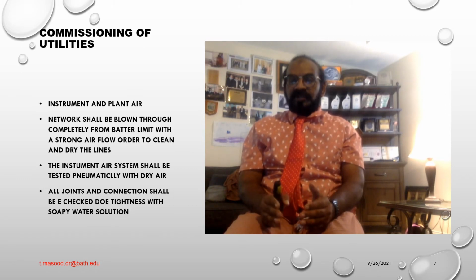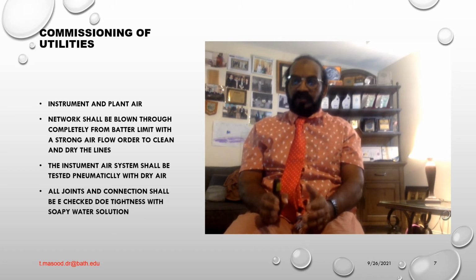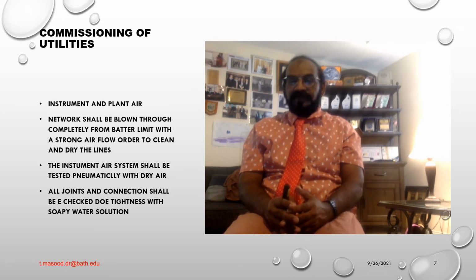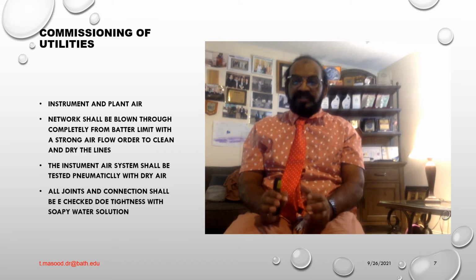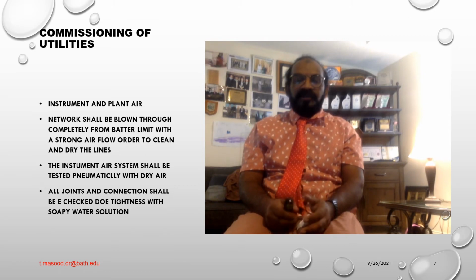The network shall be blown through completely from battery limit with strong air flow in order to clean and dry the lines. The instrument air system shall be tested pneumatically with dry air. All joints and connections shall be checked for tightness with a soapy water solution. Header and branch lines shall be blown through with a high flow rate of air. During all these tests, the instruments supplied with air shall be carefully isolated from the system.